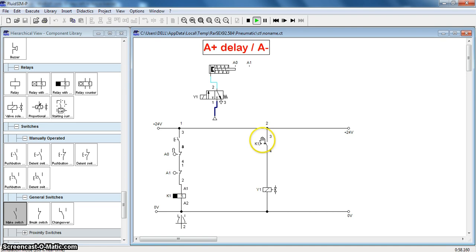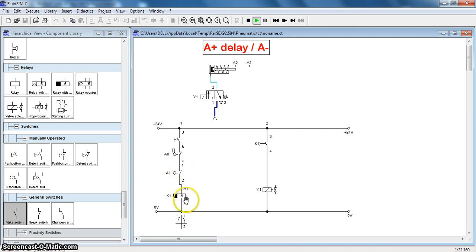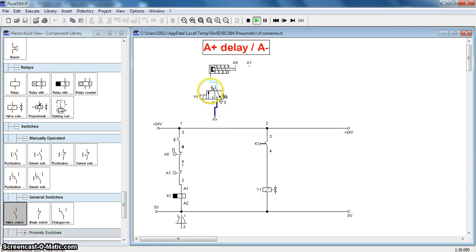When relay K1 gets activated or energized, Y1 gets charged. When Y1 gets charged, this piston moves in the forward direction. As soon as it leaves contact A0 and touches A1, this contact opens. When this contact opens, the connection to the relay is stopped and then the relay starts counting the delay. After a delay of 5 seconds, the relay gets deactivated and then the Y1 solenoid gets discharged. When Y1 solenoid gets discharged, the spring takes action and it returns back.